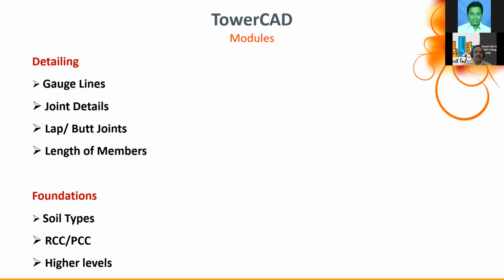We design the foundation for all the higher levels. For each tower, there are 4 higher levels: 3 meter normal tower, 3 meter extension, 6 meter extension, 9 meter extension. With 5 soil types and 4 exposure conditions, that's 20 combinations. So 20 into 4 equals 80 foundations for one type of tower. This is the challenge.